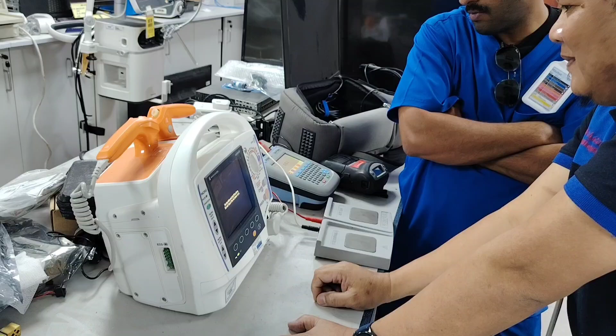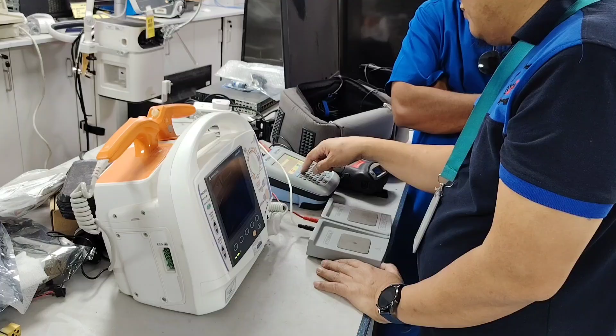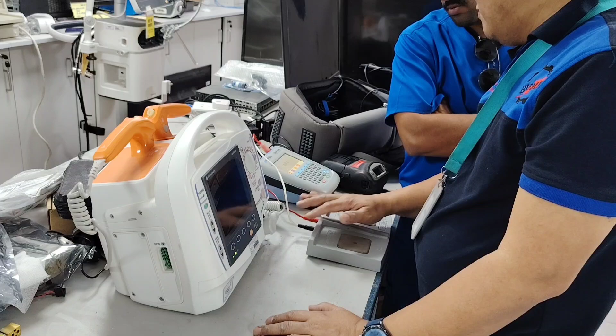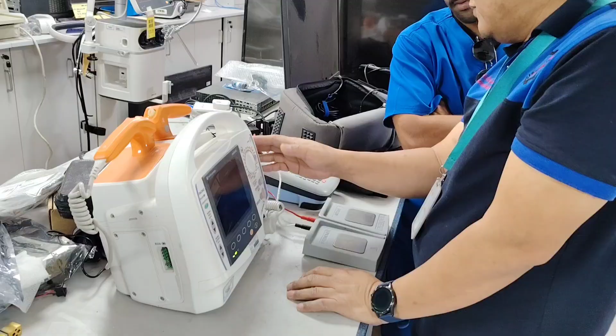Now start our real job for the biomed. First, we already select the parameters here in the defibrillator. We are checking the defibrillator paddles. So what is the biomed first check? Select this analyzer to joules. So this is our load resistance, 50 ohms. Always 50 ohms, every defibrillator, this is the standard. You can change the load in our analyzer, but our standard here is 50 ohms.